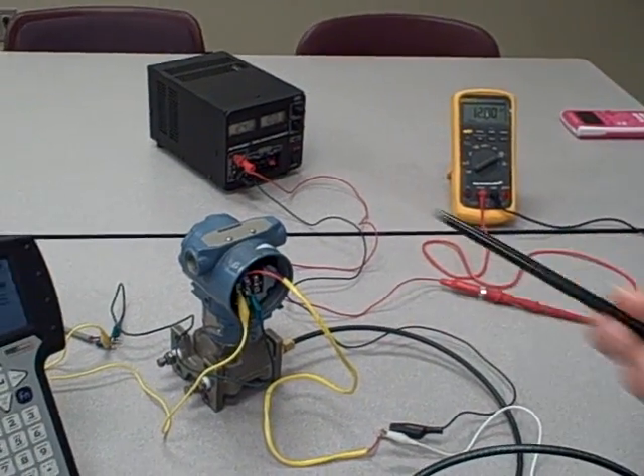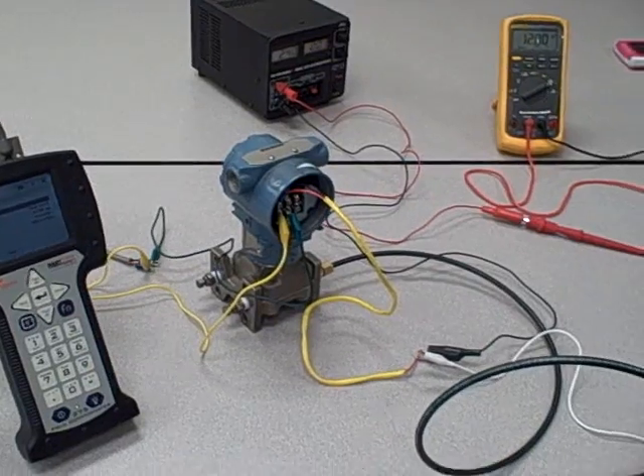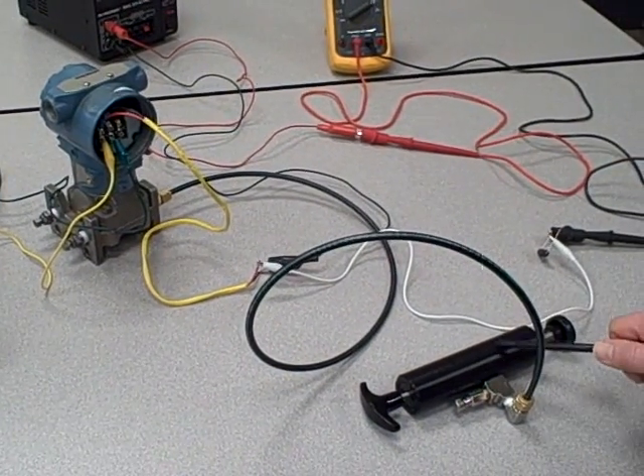The present calibrated range in the transmitter is 0 to 1,000 inches of water, and we're applying about 500 inches of water air pressure using this pump.